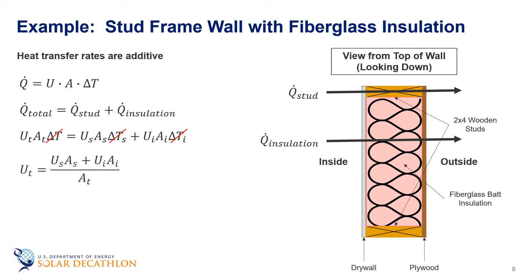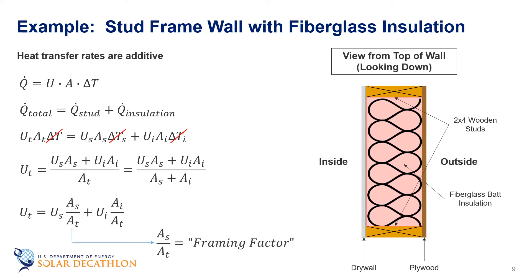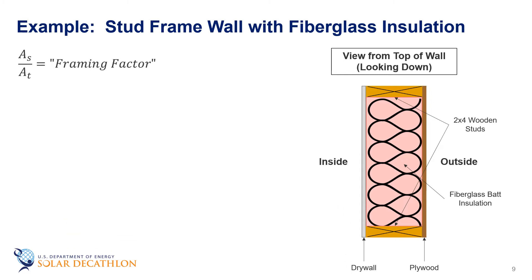Solving for U total, we get U times A for the stud plus U times A for the insulation over the total area of the wall, which is the area of the studs plus the area of the insulation. Simplifying this further, we can show this as U-stud times A-stud divided by A-total plus U-insulation times A-insulation divided by A-total. The ratio of A-stud to A-total is called the framing factor, or how much frame there is compared to the total area of the insulated wall. The remainder can be insulation.